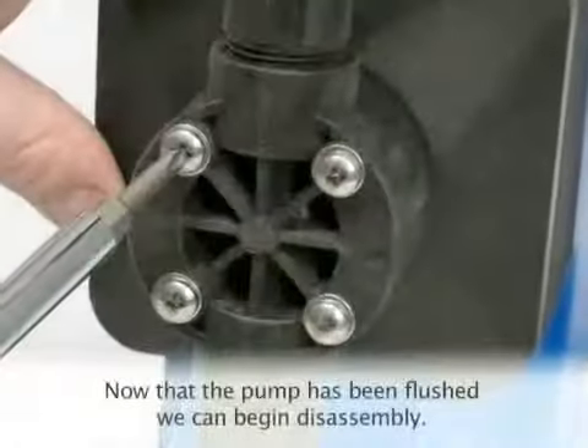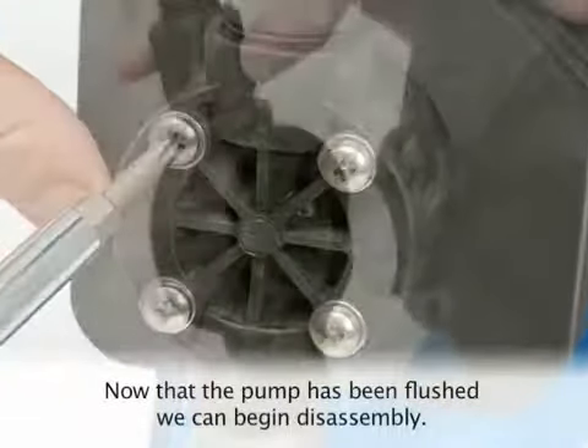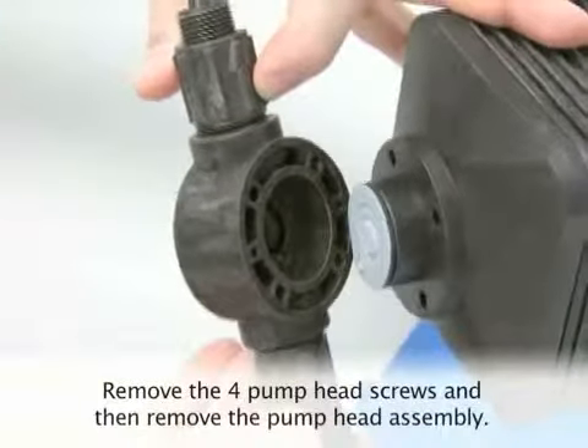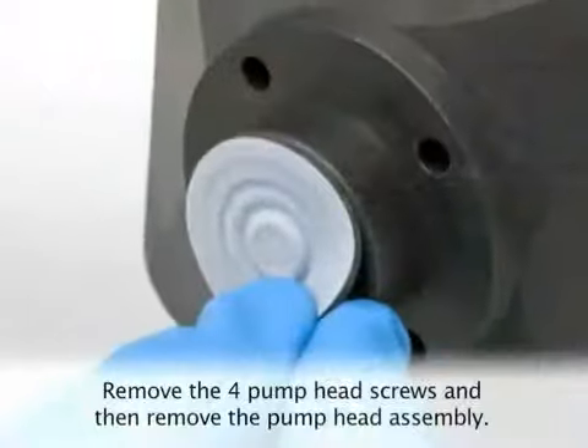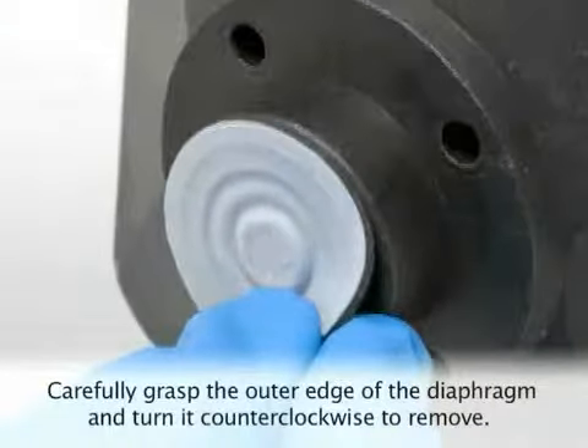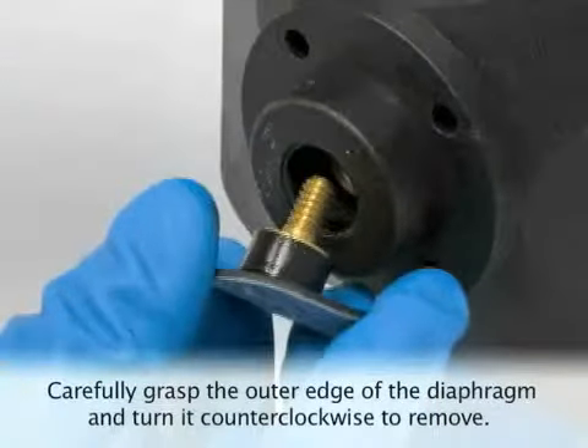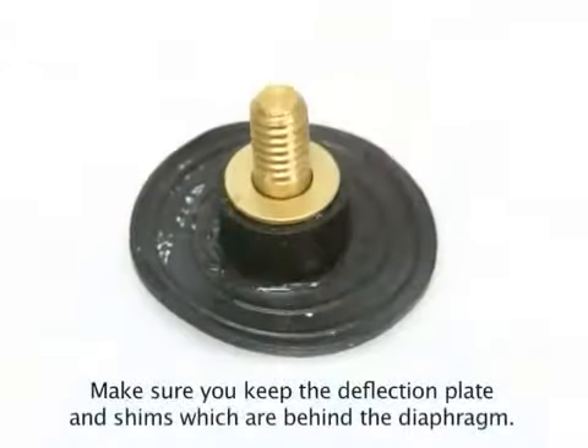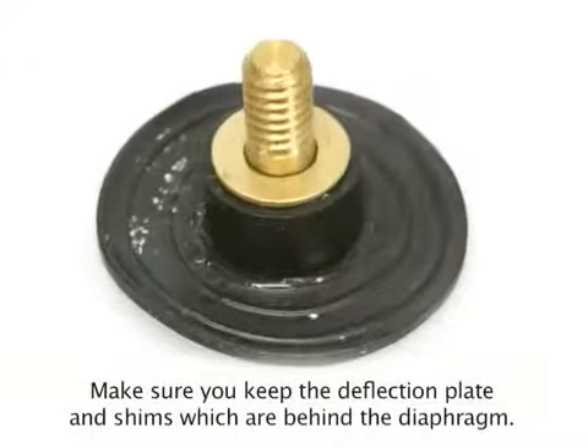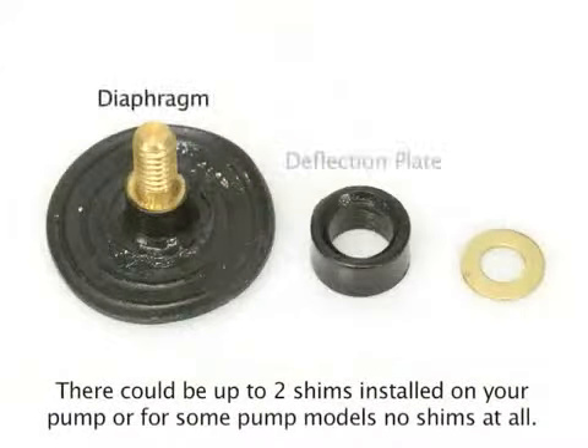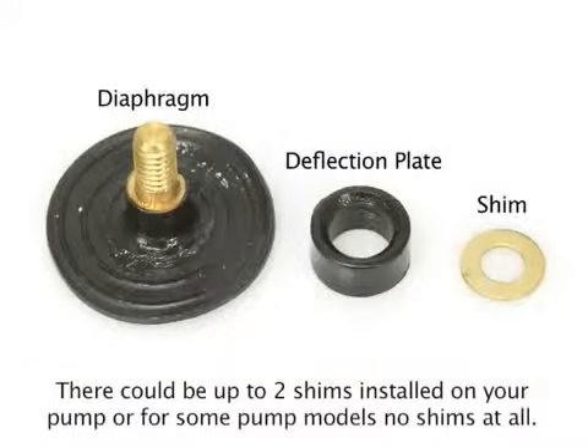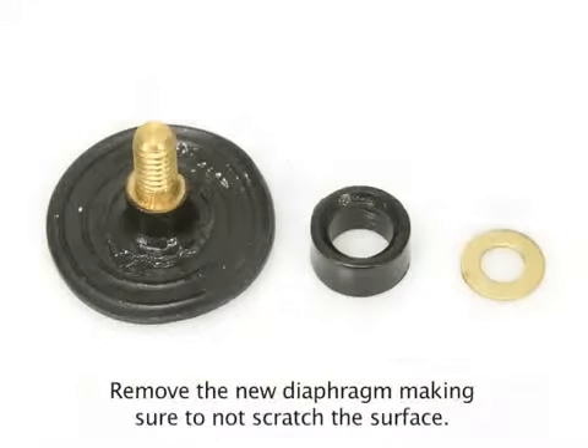Now that the pump has been flushed, we can begin disassembly. Remove the 4 pump head screws and then remove the pump head assembly. Now we can remove the diaphragm by carefully grasping the outer edge and turning it counterclockwise to loosen and remove. Make sure you keep the deflection plate and shims which are behind the diaphragm. There could be up to 2 shims installed on your pump, or for some pump models, no shims at all.